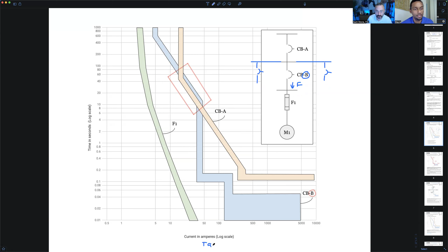All right, so I'm looking at the time current curve. There's actually two different ways we could do this. One of the two ways is a correct answer choice. Do you remember from last night? There's two main changes we can make, right? What happens if I change the tap setting? You'll move horizontally on the scale. Yeah, tap setting has to do with our amps. So that's a horizontal movement.